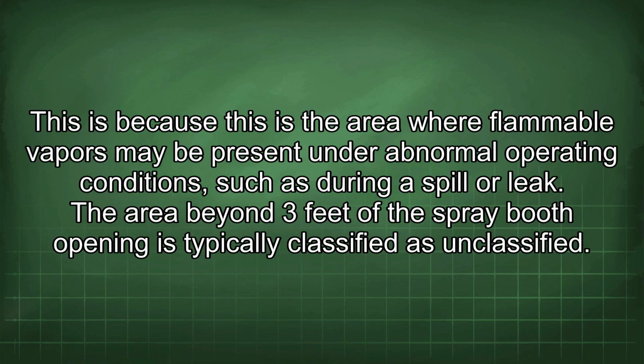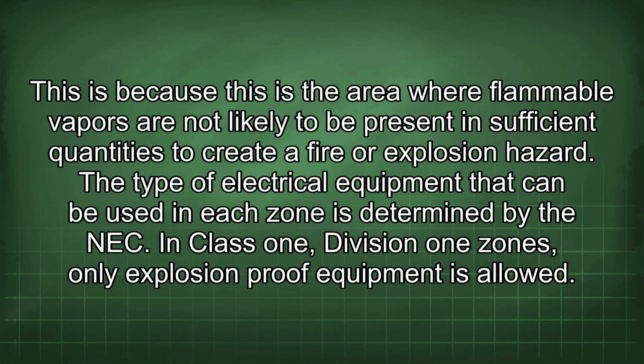This is because this is the area where flammable vapors may be present under abnormal operating conditions, such as during a spill or leak. The area beyond 3 feet of the spray booth opening is typically classified as unclassified. This is because this is the area where flammable vapors are not likely to be present in sufficient quantities to create a fire or explosion hazard. The type of electrical equipment that can be used in each zone is determined by the NEC. In Class 1, Division 1 zones, only explosion-proof equipment is allowed.